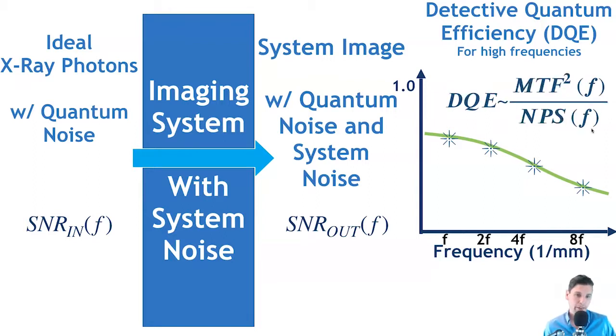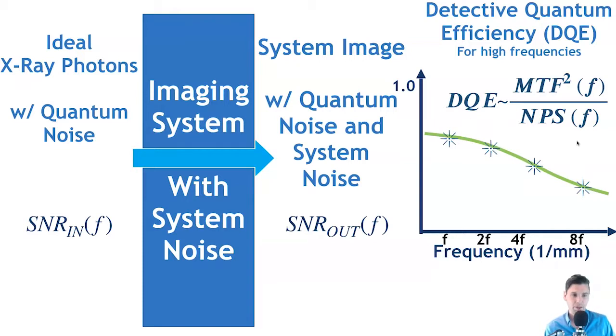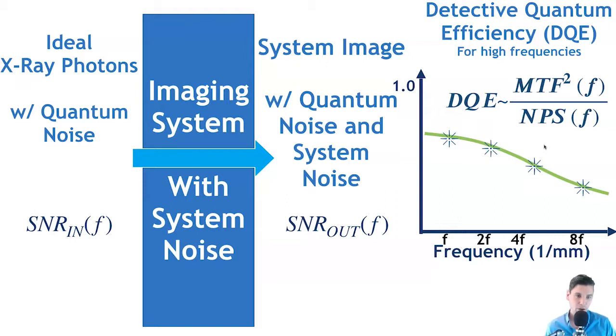We can make DQE curves as a function of spatial frequency to see how efficient the system is. A perfect detector with infinitely small pixels would have a DQE of 1 for all spatial frequencies, but such systems don't exist. In practice, we compare DQE curves between systems to assess how efficiently each captures the inherent information in our image. The DQE can also be expressed as the MTF squared divided by the noise power spectrum, which is why we discussed those two quantities — less blurring means a higher DQE.